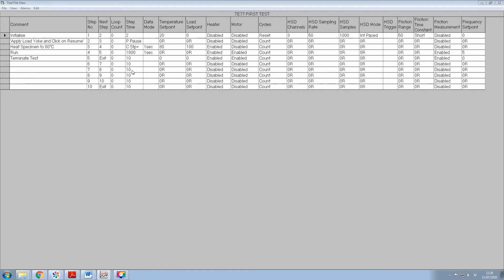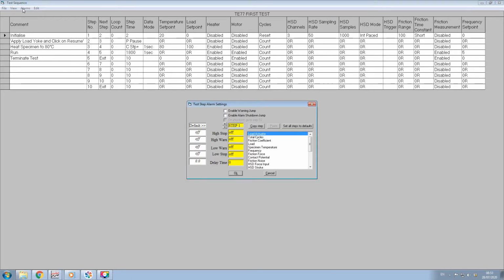Don't forget to have both the charge amplifier enabled and data mode set if you want to record any data. If you wish to run a test unsupervised, it is sensible to set alarms in the test sequence file. Click on Alarms on the toolbar. This allows the user to program high and low level warning and shutdown alarms on all analog, pulse counting and derived channels on a step-by-step basis.